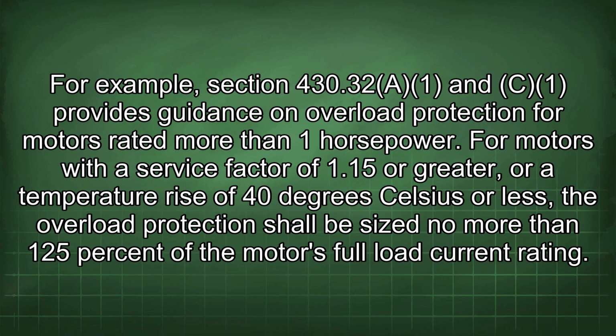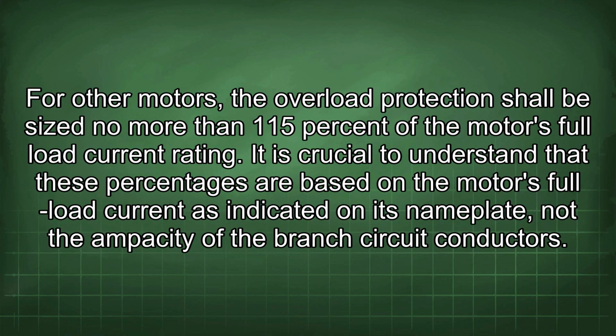For motors with a service factor of 1.15 or greater, or a temperature rise of 40 degrees Celsius or less, the overload protection shall be sized no more than 125% of the motor's full load current rating. For other motors, the overload protection shall be sized no more than 115% of the motor's full load current rating. It is crucial to understand that these percentages are based on the motor's full load current as indicated on its nameplate, not the ampacity of the branch circuit conductors.